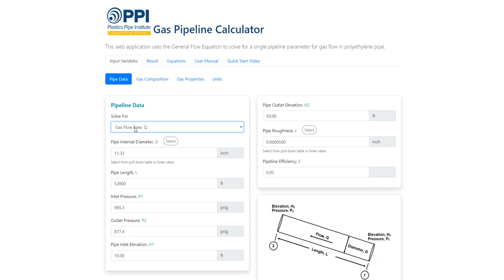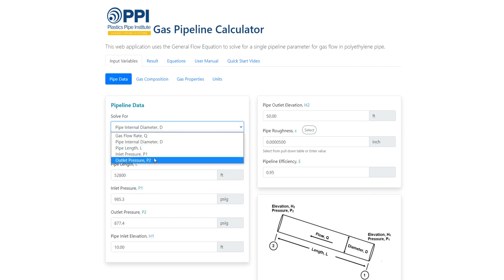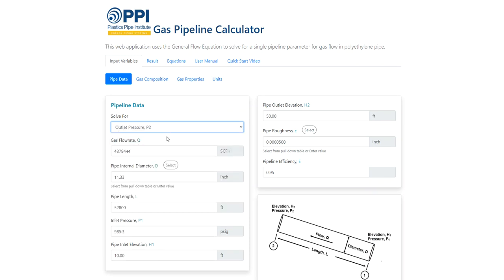The four data fields after the solve-for field will change based on what is selected. For example, if gas flow rate is chosen, the user must input pipe internal diameter, pipe length, inlet pressure, and outlet pressure. If internal ID is selected, gas flow rate, pipe length, inlet pressure, and outlet pressure must be entered. If outlet pressure is desired, gas flow rate, pipe internal diameter, pipe length, and inlet pressure must be entered. The pull-down menu on the pipe internal diameter field can be used to select the pipe size and DR for polyethylene pipe, for which internal diameter will be calculated.